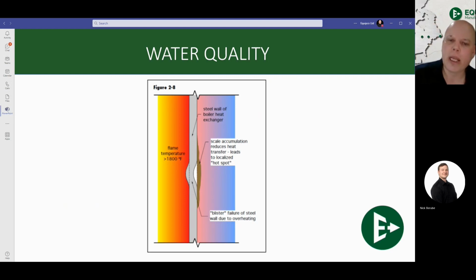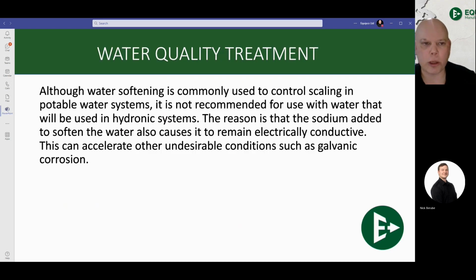So the buildup of scale now acts like an insulator. If the scale's there, it's insulating that piece of steel, so the water's not touching it, so it's not able to move that heat away. And that's what leads to the blistering and eventually cracking of a heat exchanger. That's what it's going to look like.